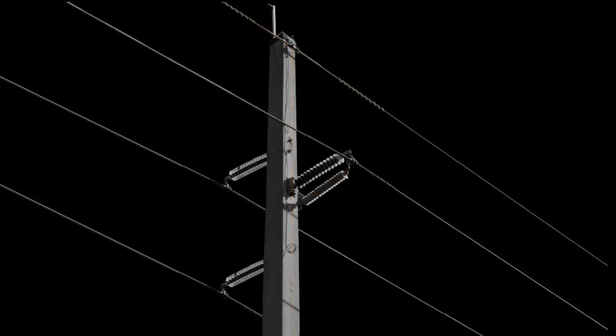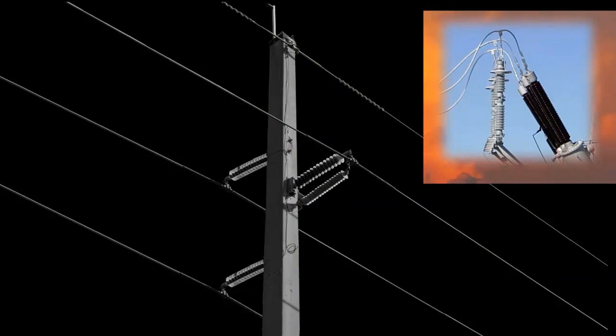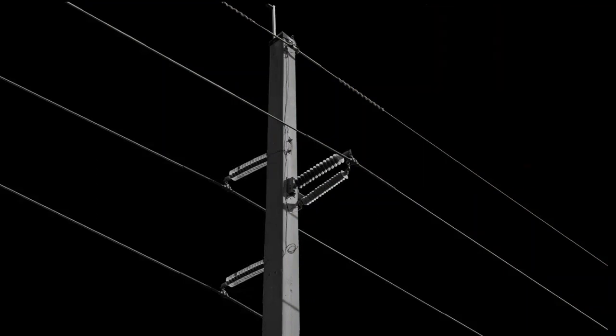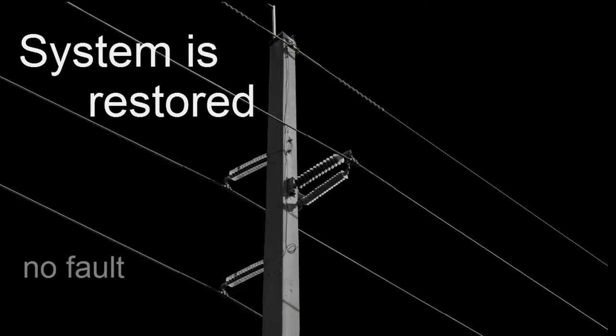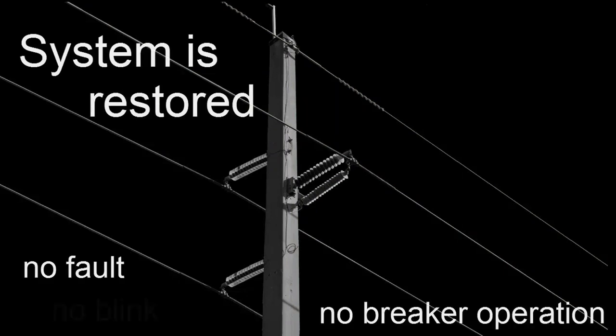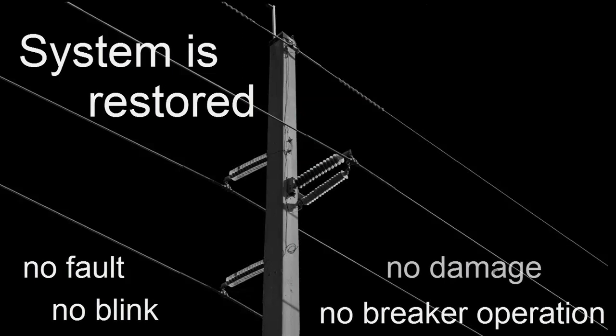The lightning current is only a few thousand amps in amplitude and is easily handled at the station by the station arrestor mounted there. The strike is over, the arrestor turns off, and the system is restored without a fault. No breaker operation. No blink on the system. No potential damage to the insulators.